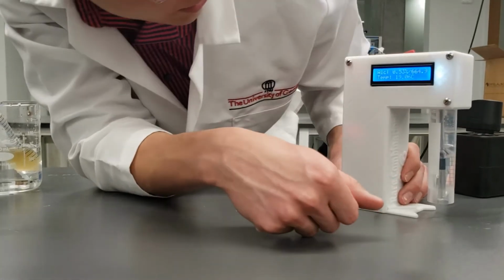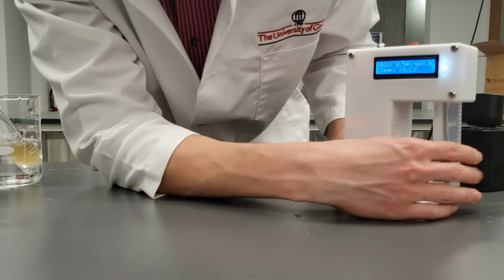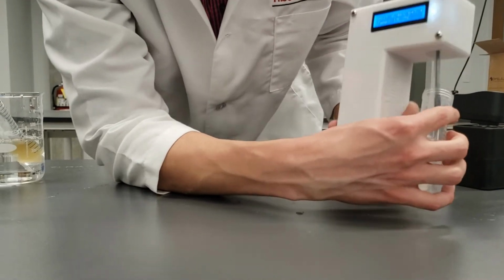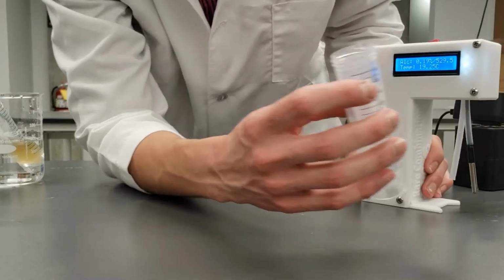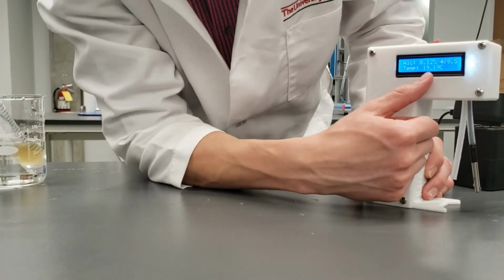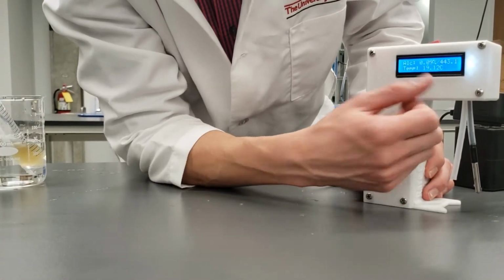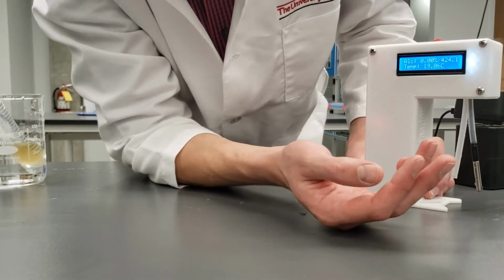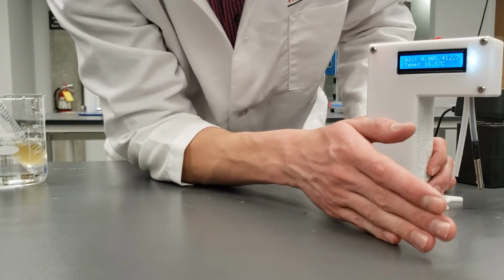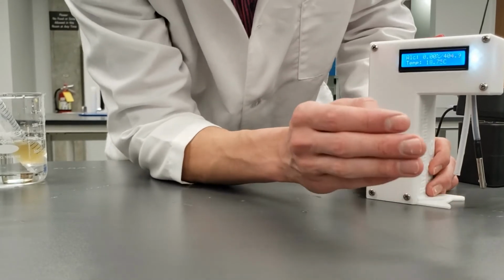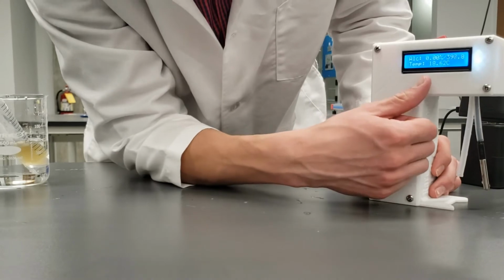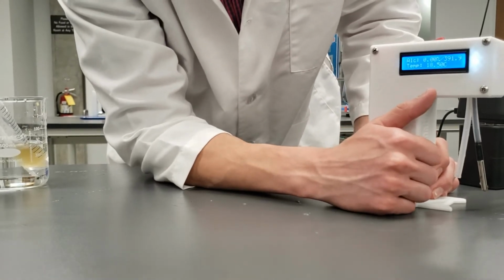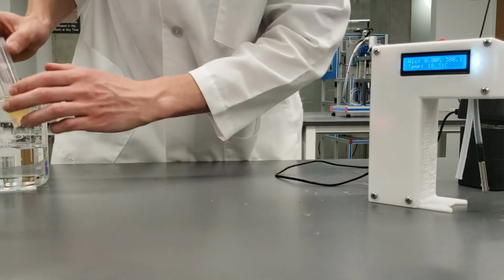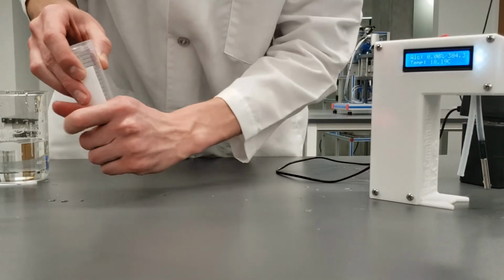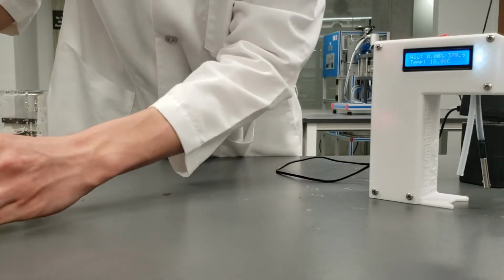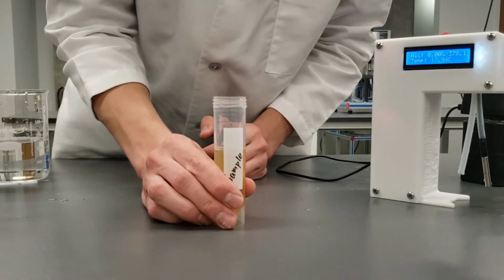So as you're doing this, what you're going to want to do is try out different temperatures around room temperature. Now, your calibration temperature might be as low as about 15 degrees C, or as high as maybe even 30 degrees C. So just adjust your 0.5% standard accordingly until you get 0.5% alcohol content reading on the screen. So now that we have our calibration temperature, we can take our sample that we have here.